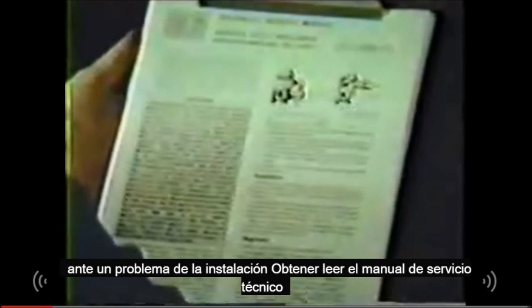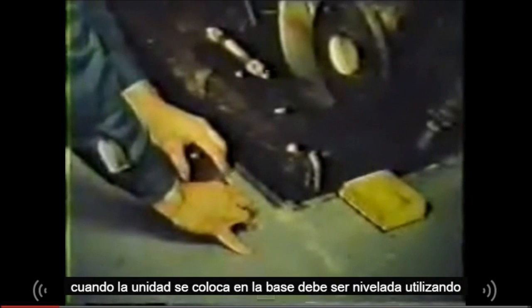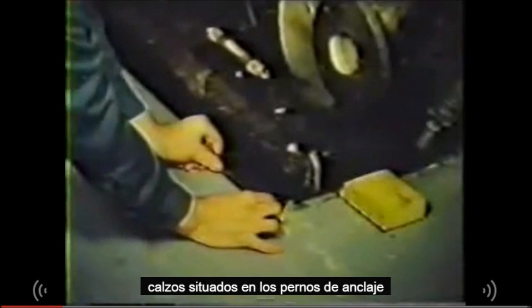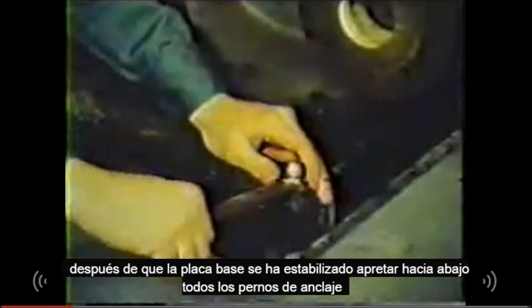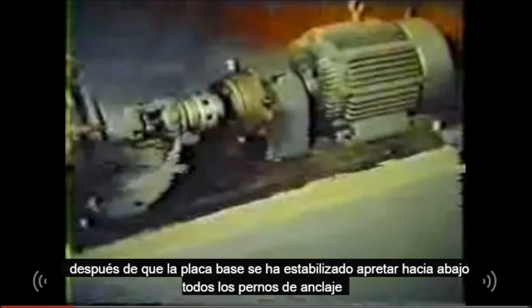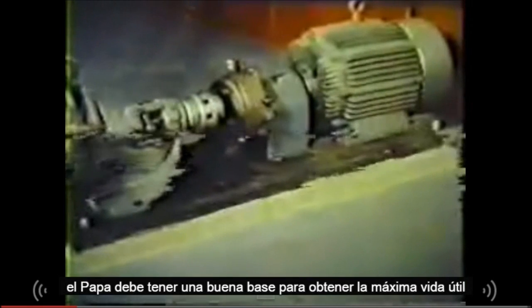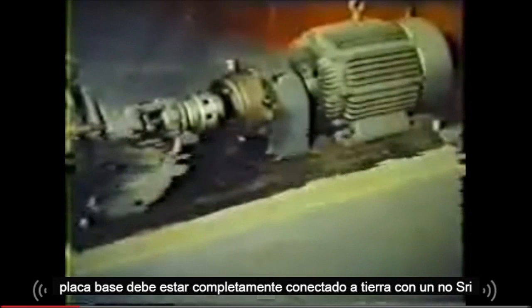Before installation of the pump, obtain and read the technical service manual furnished by the manufacturer. Be sure to read all warnings and caution information. When the unit is placed on the foundation, it should be leveled by using shims located at the anchor bolts. On a long base, additional shims may be needed on the long sides of the base plate. After the base plate has been leveled, tighten down all anchor bolts. The pump should have a good foundation. To obtain the maximum service life, the base plate should be completely grouted with a non-shrink type grout.